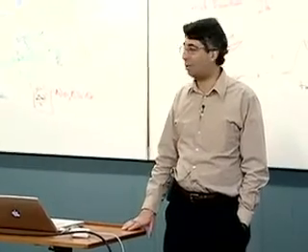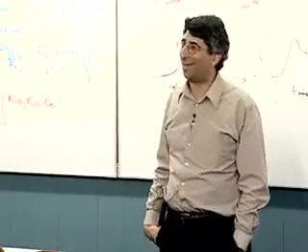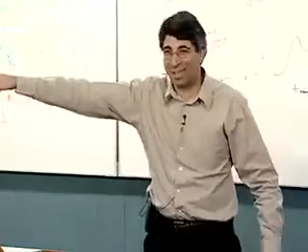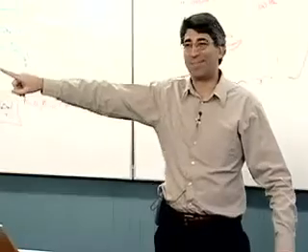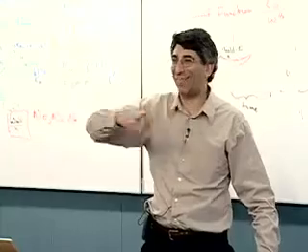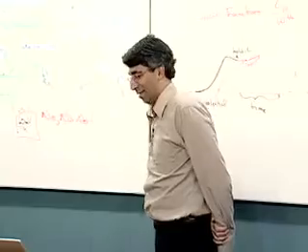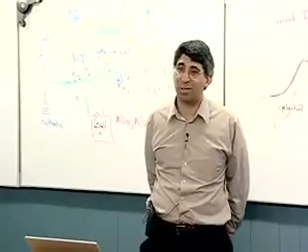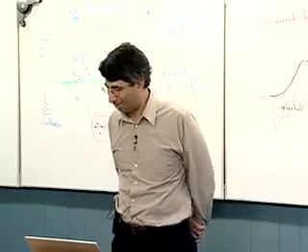So, for example, you have your voltage and your current outputs, and you decide, and my students have done this actually, that you'd like the potentiostat on that side of the lab and your electrochemical cell on that side of the lab. Okay, now they're not scanning at 100,000 volts per second, but this is still annoying. You know, there's going to be IR loss in that line and whatnot, and you could expect that at some very high scan rate, things are going to mess up. Likewise, if you decide you're not going to use coax cables, you expect you'll pick up all kinds of noise that you might interpret as cyclic voltammetric events.